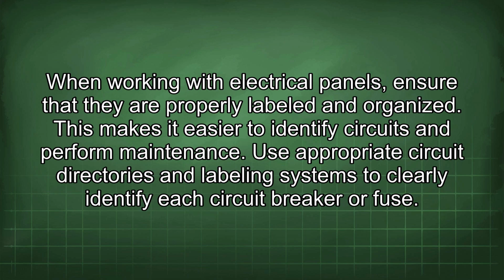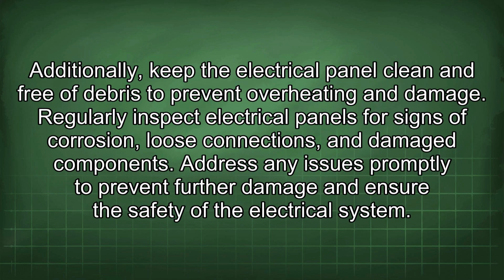When working with electrical panels, ensure that they are properly labeled and organized. This makes it easier to identify circuits and perform maintenance. Use appropriate circuit directories and labeling systems to clearly identify each circuit breaker or fuse. Additionally, keep the electrical panel clean and free of debris to prevent overheating and damage. Regularly inspect electrical panels for signs of corrosion, loose connections, and damaged components. Address any issues promptly to prevent further damage and ensure the safety of the electrical system.